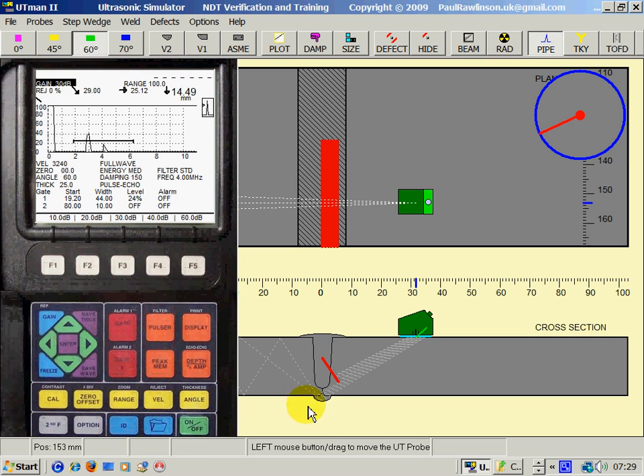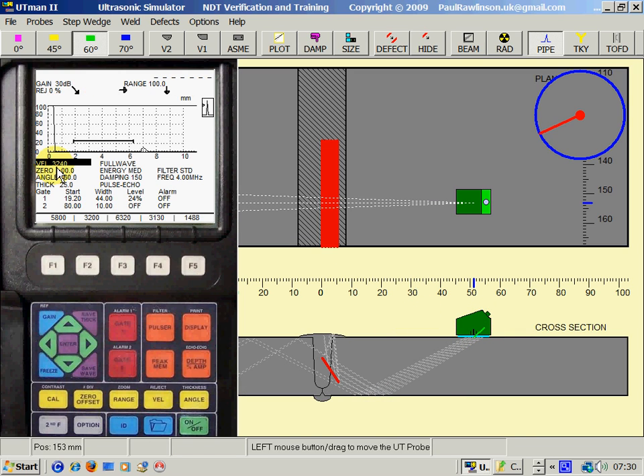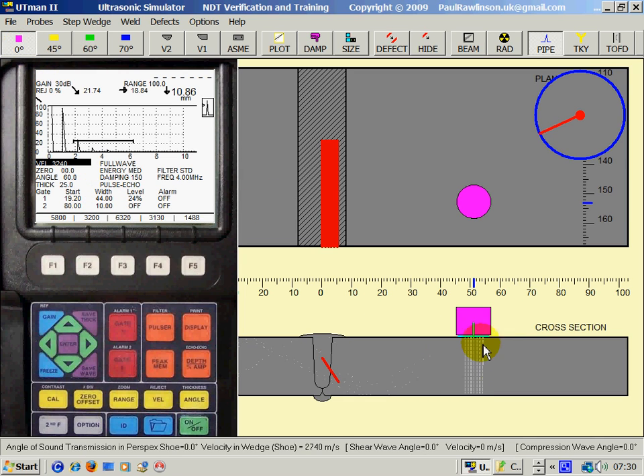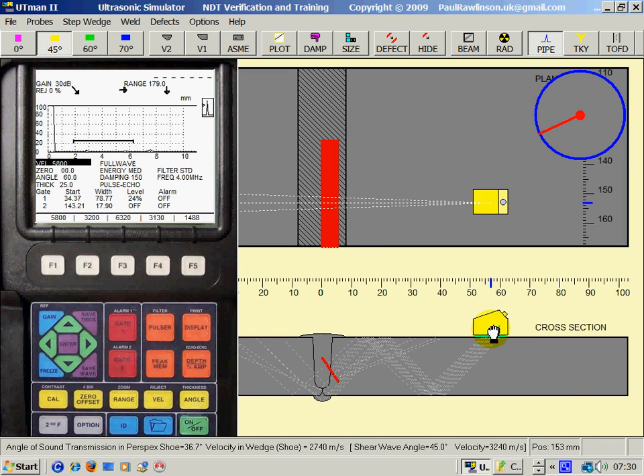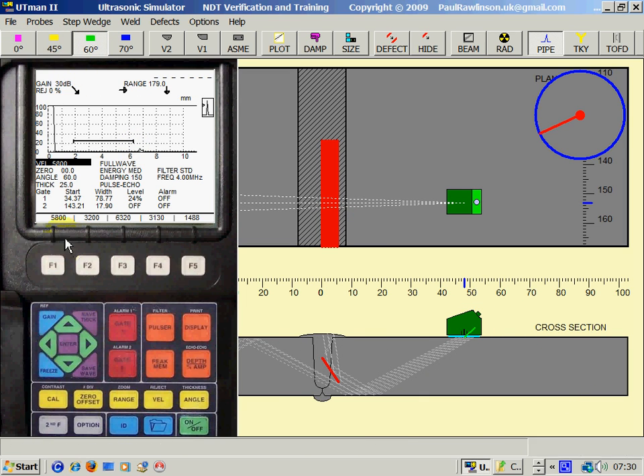Now for correct calibration, we have to set the angle. In this case, this is a 60. We can go on the F4 key to quickly set 60. We have to set the velocity. In this case, this is shear wave, so it is about 3,240 meters per second. If we're on a zero probe, which is a compression wave, we'd have to set that to about 5,800 meters per second. I'll put it back on the 60, which is shear wave, so I'll put it on about 3,200 meters per second.